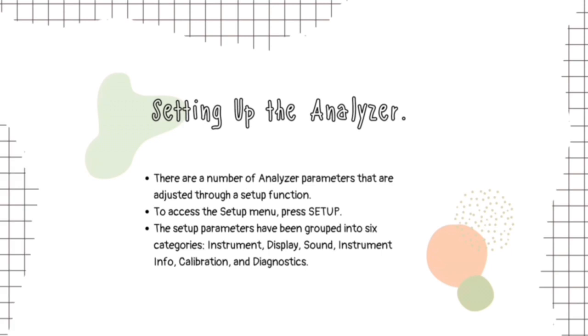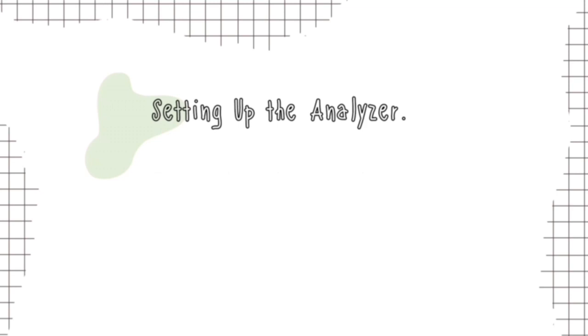After that, we must set up the analyzer. There are a number of analyzer parameters that are adjusted through a setup function. To access the setup menu, press setup. The setup parameters have been grouped into 6 categories, which are instrument, display, sound, instrument info, calibration, and diagnostic.